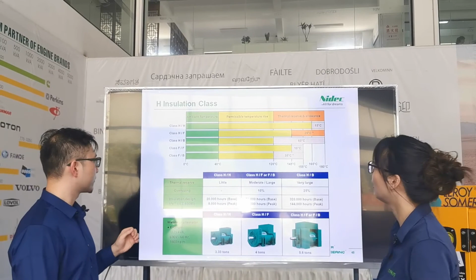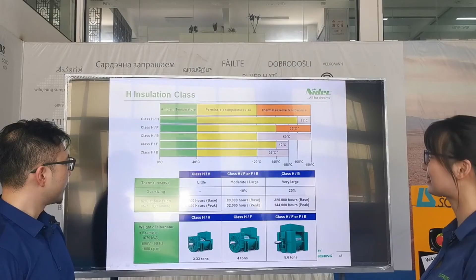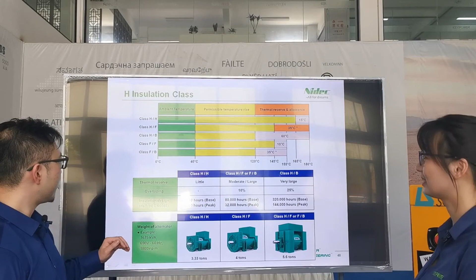For insulation design life, with different insulation class and different temperature range combinations, the insulation design life is totally different. For example, in class HH, the insulation design life could be around 20,000 hours, about 4 years. In HF or FB, the life could be around 80,000 hours, about 10 years. And in HB, the life could be around 320,000 hours, more than around 40 years.